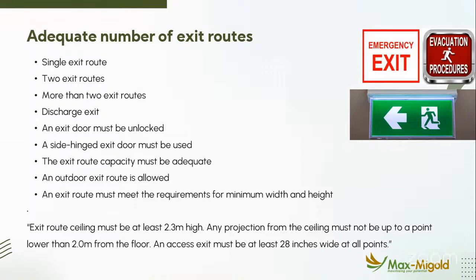Based on the number of people working there, yes, they have 3 exits. One is controlled, because that's a turnstile. All right. So it means that if there is a power outage, people cannot go out. So that means effectively they have 2 exits. Out of the 2 exits, there is one close to the basement, which has electrical changeover panels and everything there. That then tells me that if there is fire from that particular place, from that basement, people cannot go through the basement exit route. The turnstile will jam, because it needs power to operate. That means they'll be left with 1 exit. And if I'm not mistaken, today in that building, I saw well over 50 people. All right.